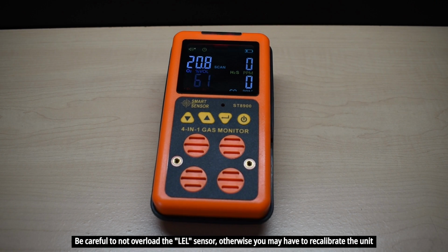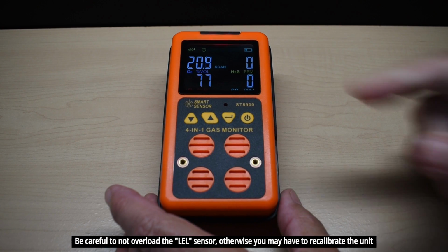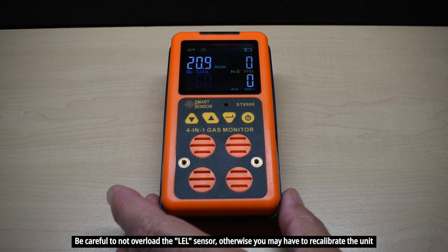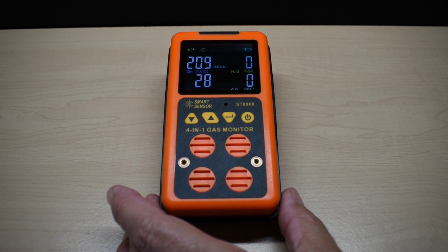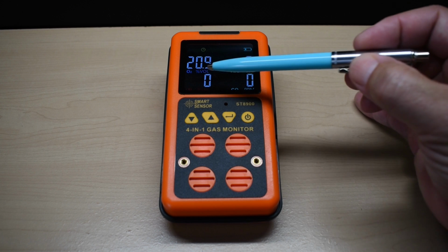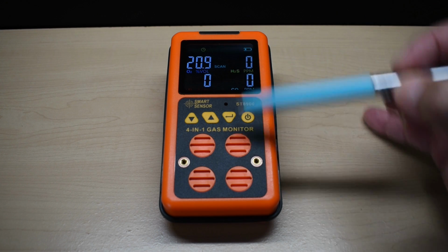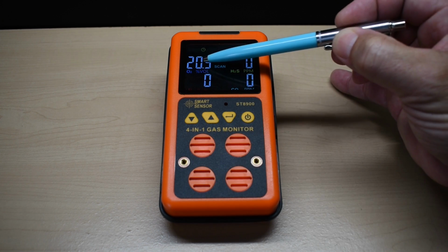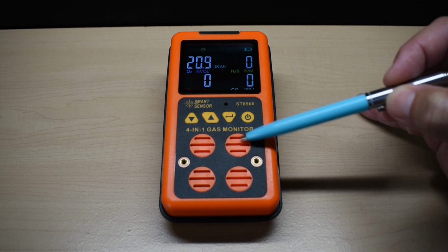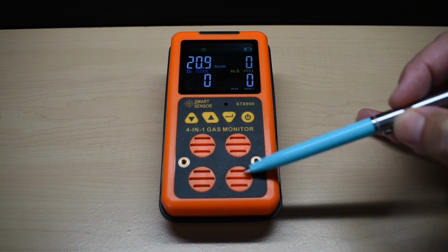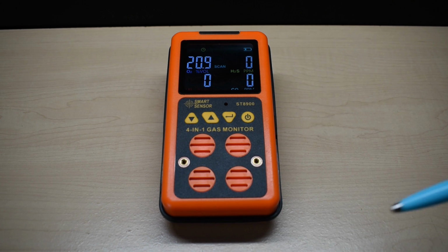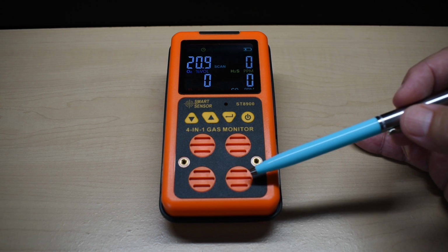You can see it shot up, and it will go back to normal very shortly. As you just saw, it worked fine, and you can see that each one of these is set up to match the sensor. So the O2 is here, LEL is there, hydrogen sulfide is here, and the carbon monoxide sensor is located right here. Now let's take a look at carbon monoxide.